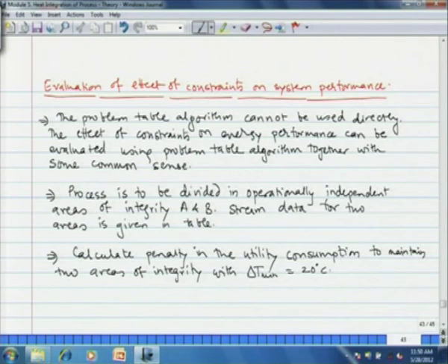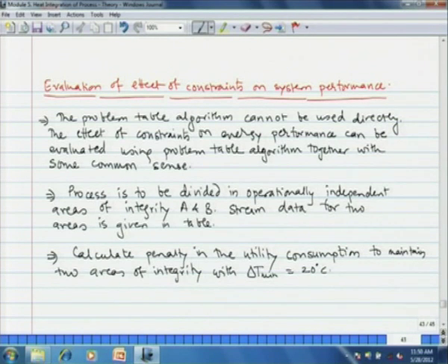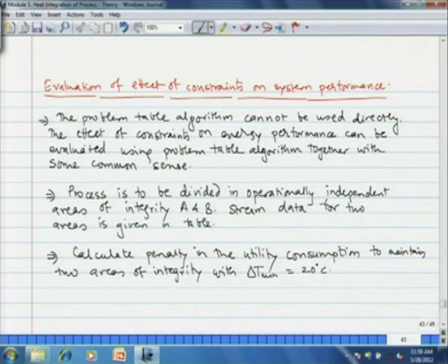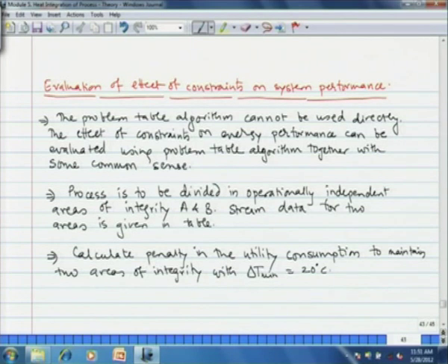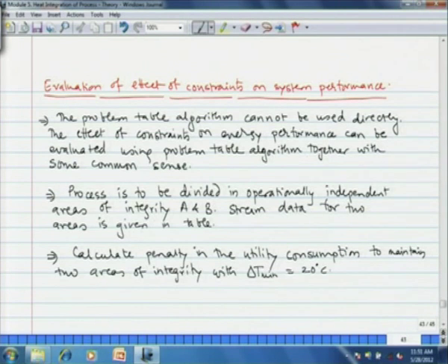One common reason for constraint is areas of integrity. The process often has logically identified sections: for example, one area of the plant is the reaction area, another is the separation area. These areas are kept separate for reasons such as start-up, shut-down, operational flexibility, or safety. They are made independent of each other by intermediate storage of process materials. Such independent areas are called areas of integrity and impose constraints on the ability for heat transfer — to maintain operational independence, two areas cannot depend on each other for heating and cooling recovery.